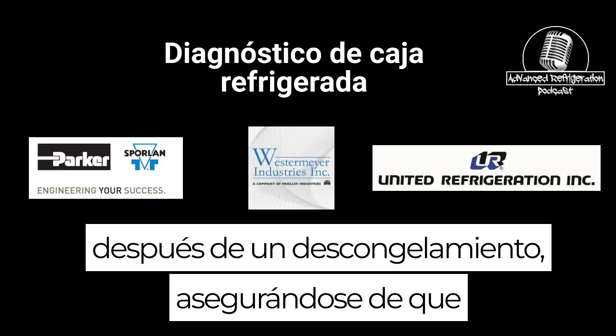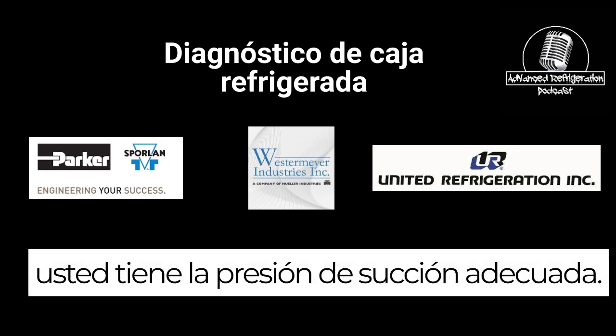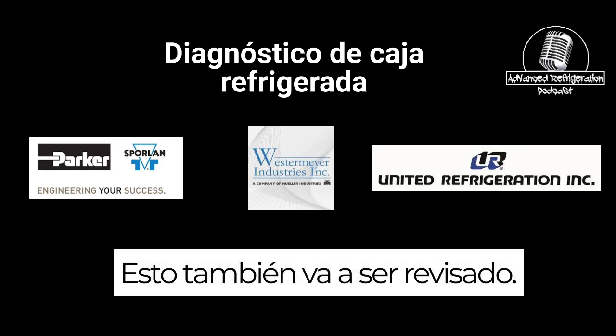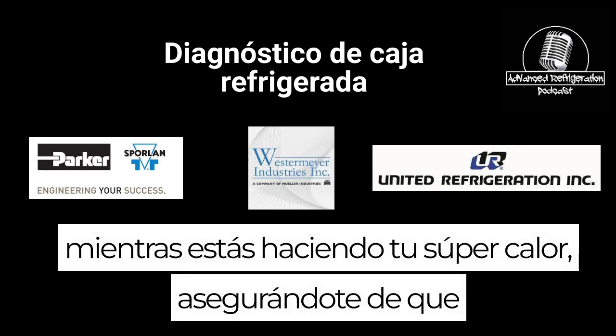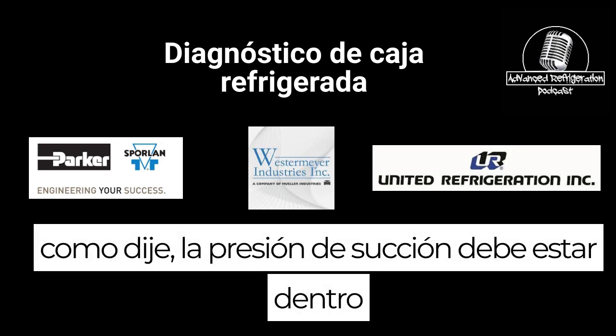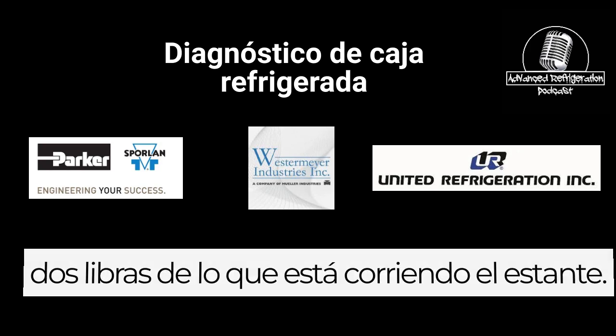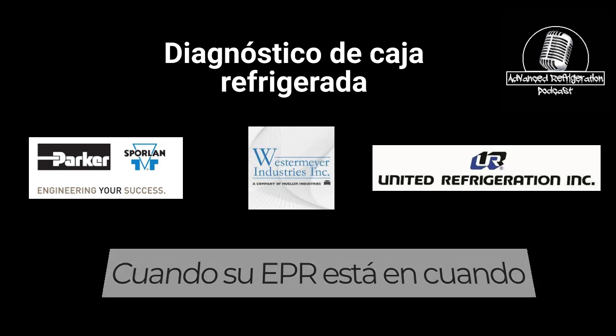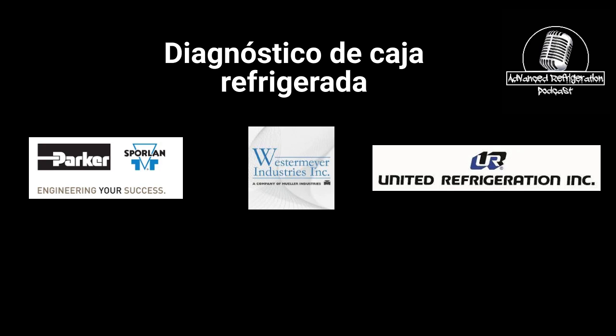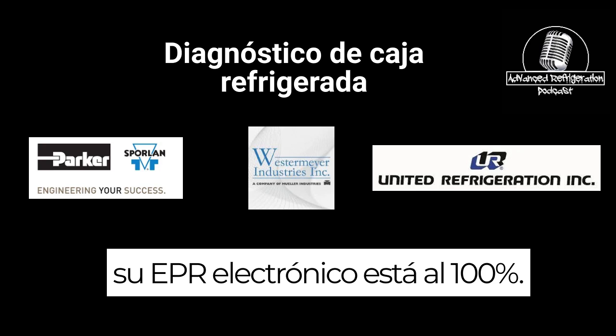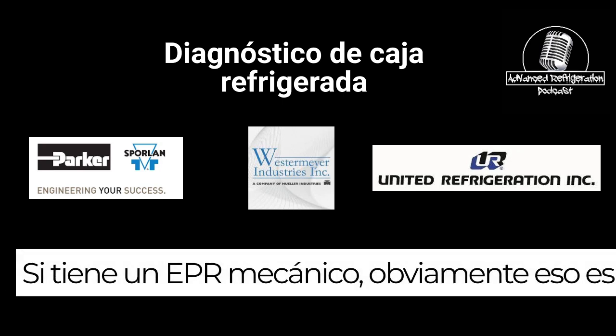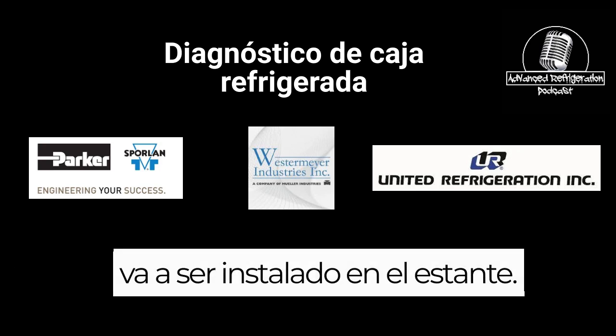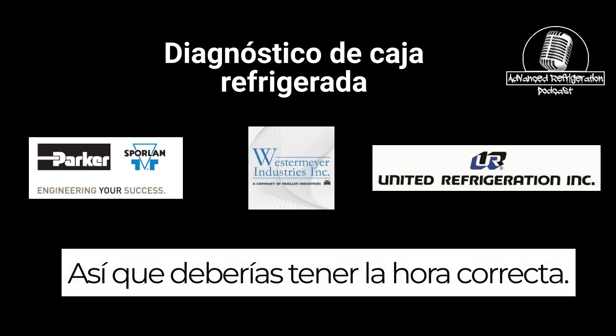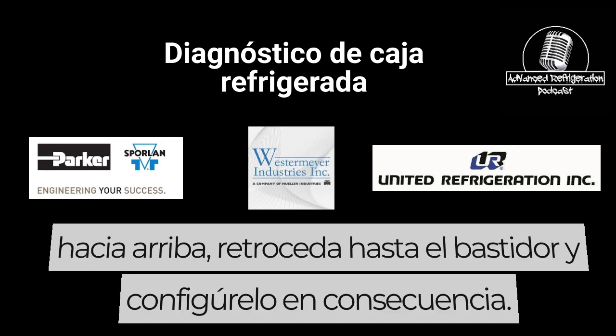Making sure down the case that you do have the proper suction pressure. This is also going to be checked while you're doing your superheat. Like I said, the suction pressure should be within 2 pounds of what the rack is running when your electronic EPR is at 100%. If you have a mechanical EPR, then obviously that's going to be set up with the rack, so you should have the correct pressure. If you don't, you're going to have to go back up to the rack and set that accordingly.